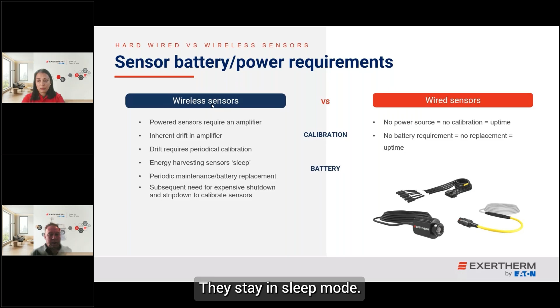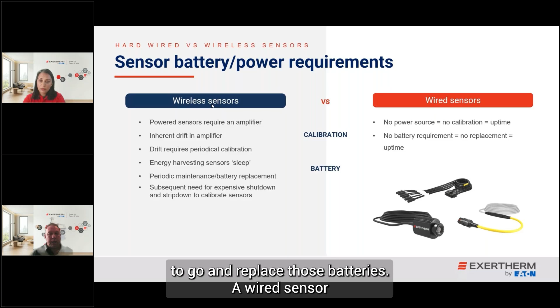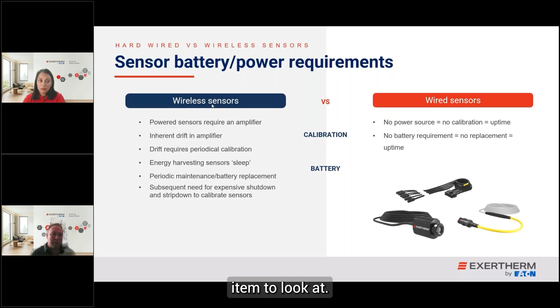Battery power sensors, exactly the same. The battery has a finite life. It will run out of life in maybe 3 to 5 years. So again, that means you've got downtime. And that battery life is determined by the number of readings, the number of requests. So if you're making lots and lots of requests, you're reducing that battery life. Again, it's that downtime, that dismantling to go and replace those batteries. A wired sensor that we provide, there's no power source, so we don't need recalibration. It's 100% uptime. You've got no batteries to replace. So again, it's uptime. It's an important topic. It's a really important item to look at.